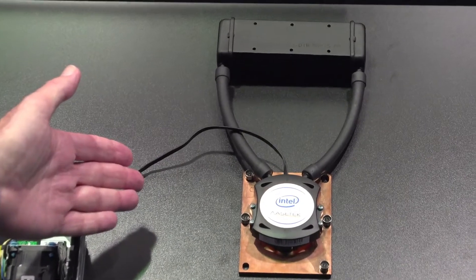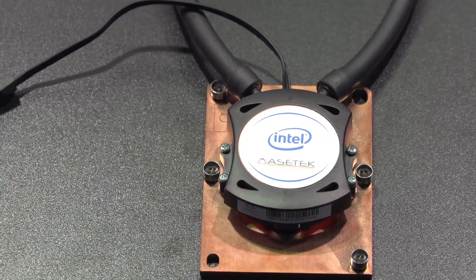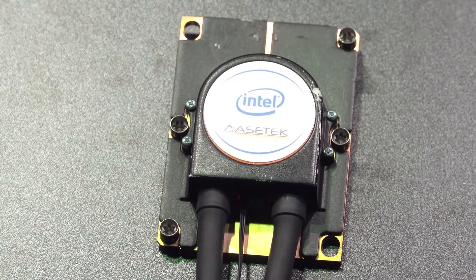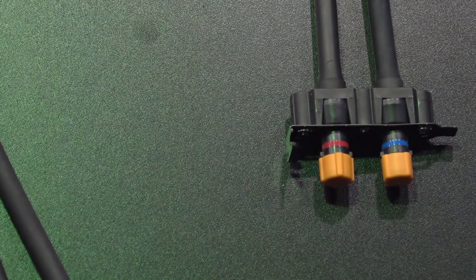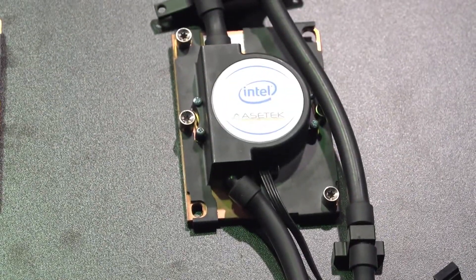This is all at the node level — how do you take that heat away from the rack? Well, one of the things happening as a result of these high-power systems is we've got people that aren't quite ready to make the leap into having a liquid-cooled data center, but still want to use these high-power processors. So we come back to Asetek's roots, which is cooling in desktop machines — just a cold plate on top of the processor and a radiator inside the machine. This technology sized for a 1U half-width server allows more wattage in the processor to be disposed of with regular air than is possible with a traditional air-cooled heat sink. We see that becoming a significant part of our business over the next year to year and a half, as these high-power processors go into data centers not yet prepared for liquid cooling.